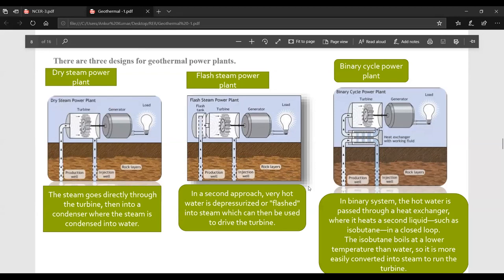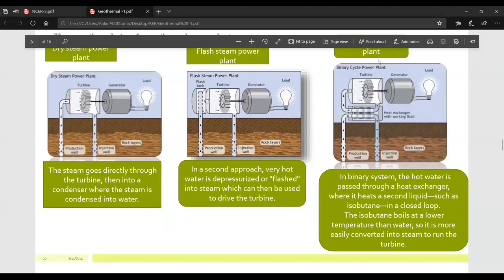In the flash steam power plant approach, very hot water is depressurized or flashed into steam, which can then be used to drive the turbine. In the binary cycle system, hot water is passed through a heat exchanger where it heats a second liquid, such as isobutane, in a closed loop.